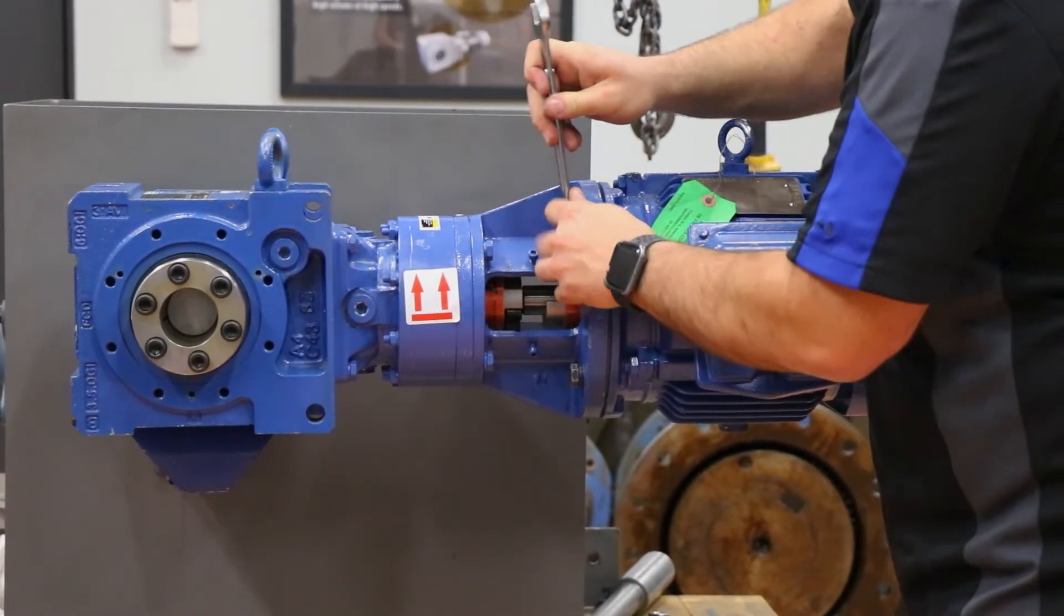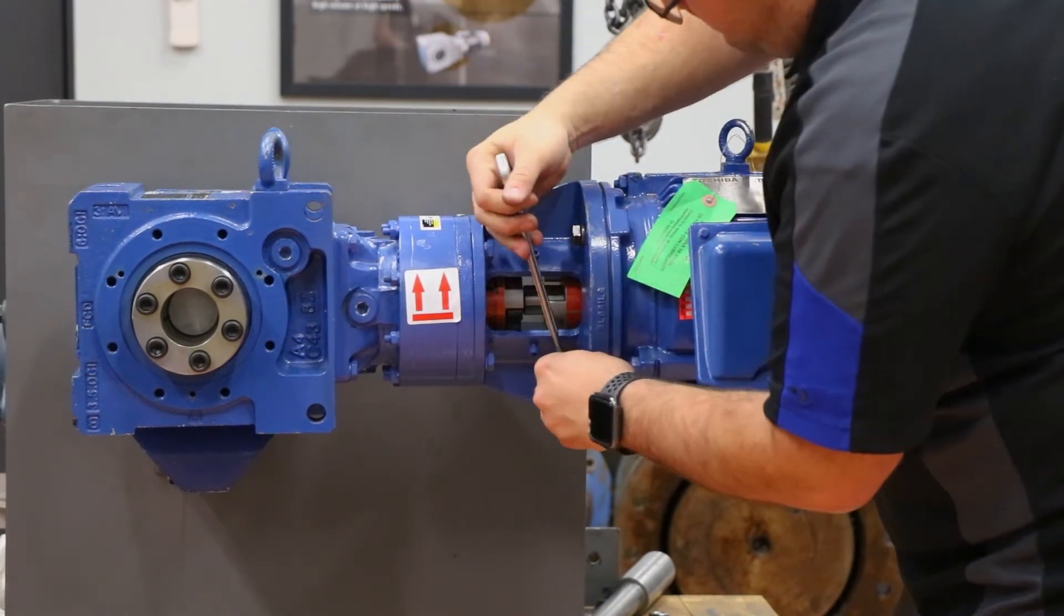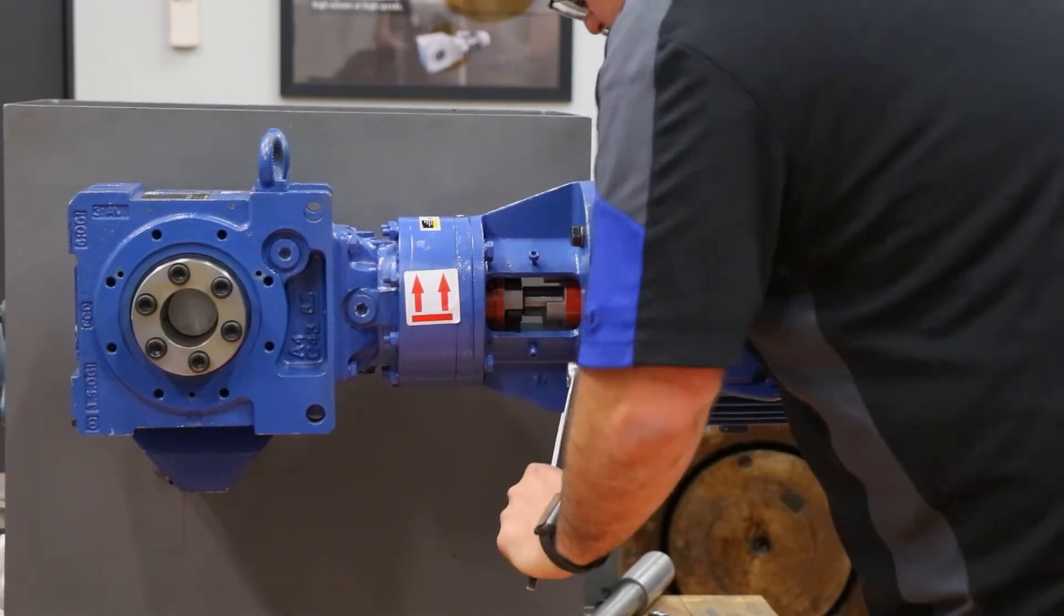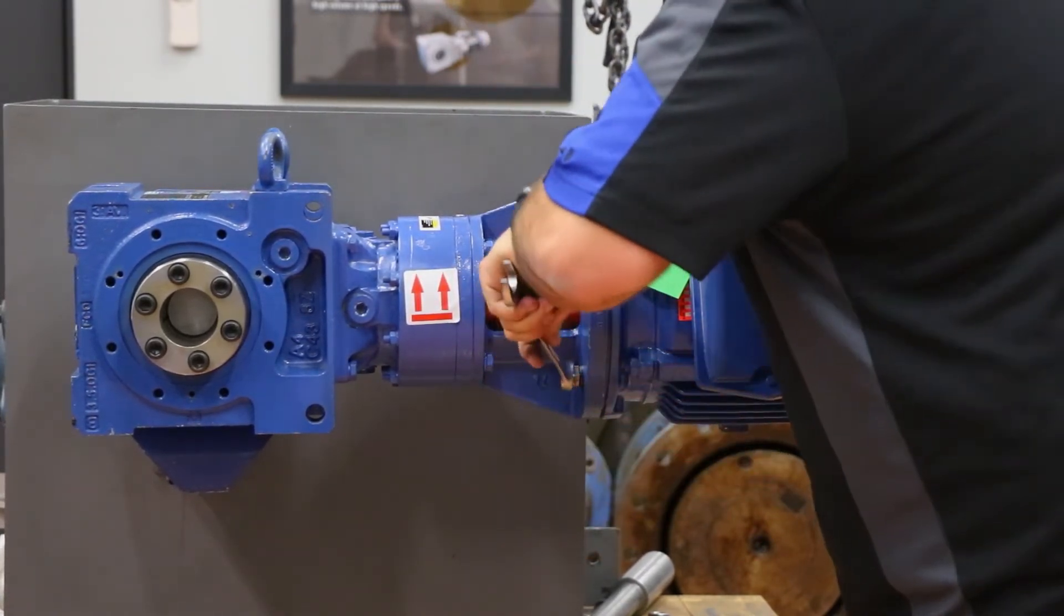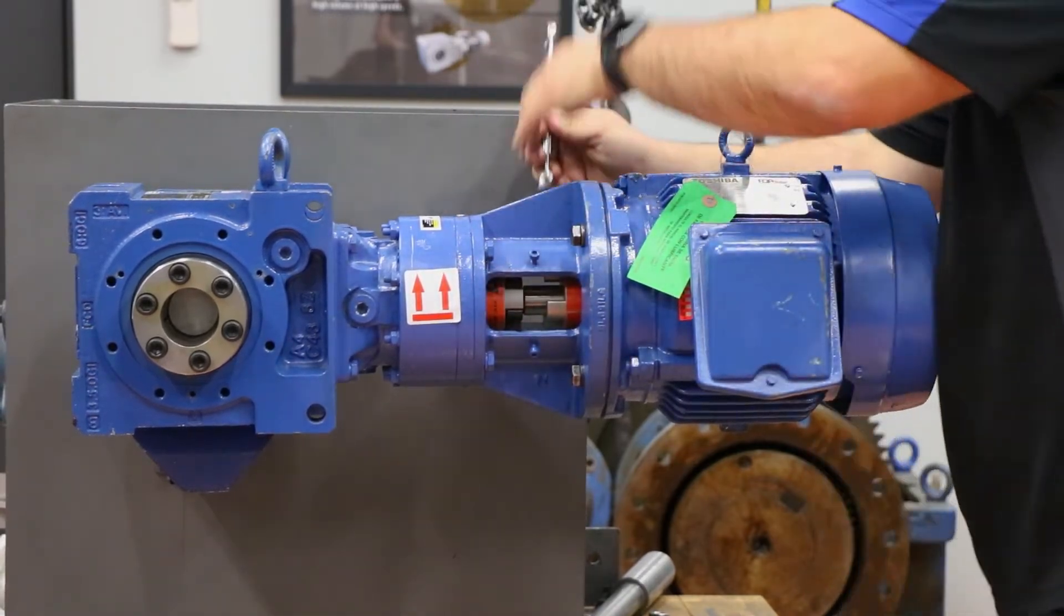Once all four of them are nice and tight and started correctly, you can go around with the wrench and tighten them up in a circular pattern. You can do a star pattern as well—it's not as critical. You just want to make sure the pilot on the motor is nice and snug to the gearbox C-face adapter.